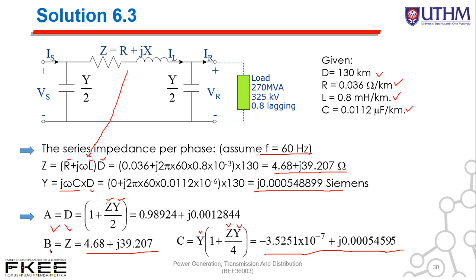So now we have the values of A, D, B, and also C. From the given value of receiving voltage line to line, the three-phase voltage at receiving is 325 kilovolt. So we can calculate the single phase receiving voltage, that is 325 divided by root 3. We got 187.64 kilovolt receiving voltage in single phase. To calculate the single phase receiving current, we can divide the receiving power by 3 times the single phase receiving voltage. So 270 divided by the value of VR, we got 479.64 ampere.